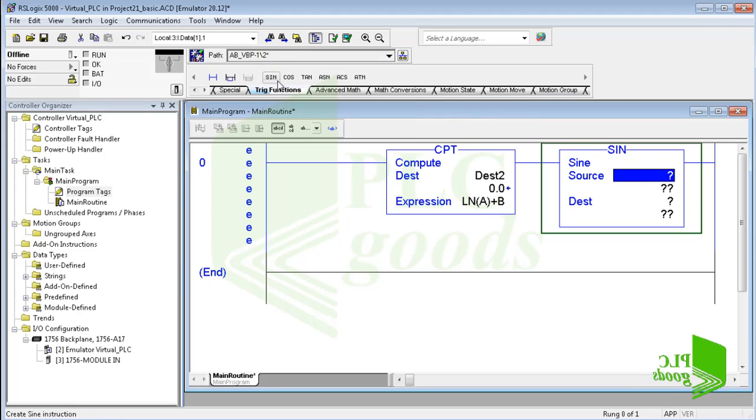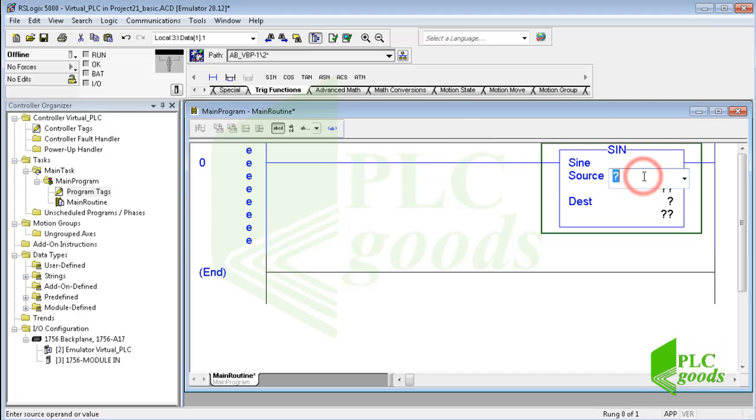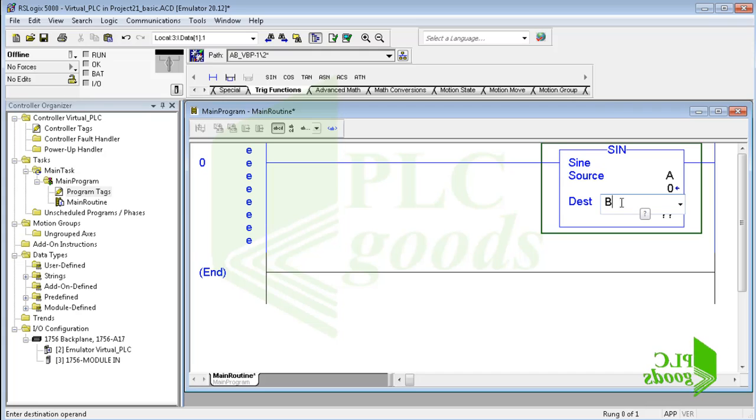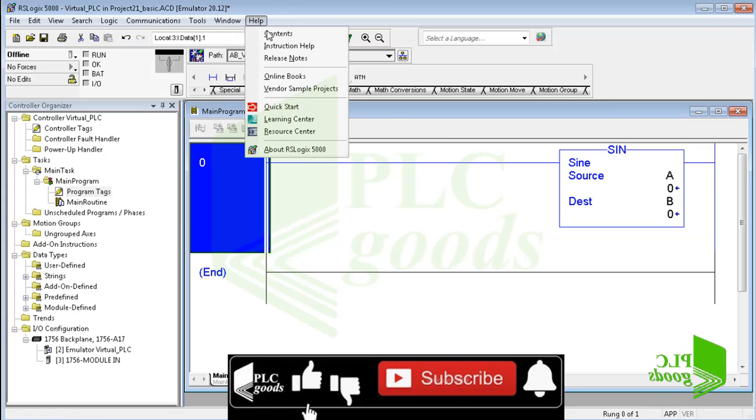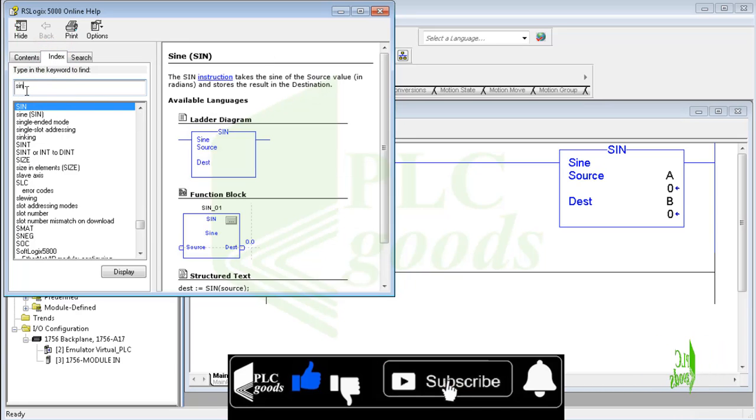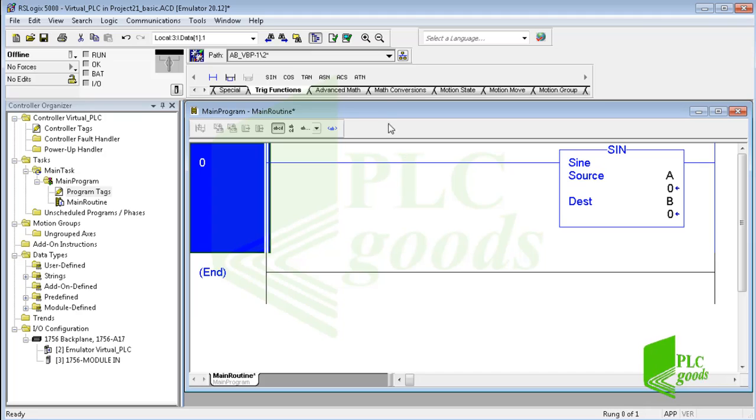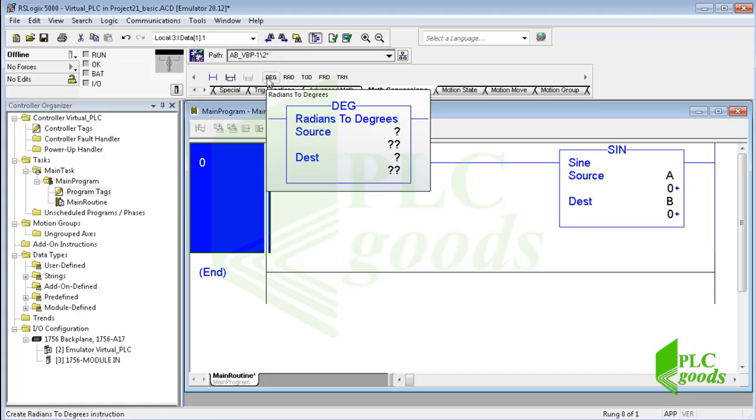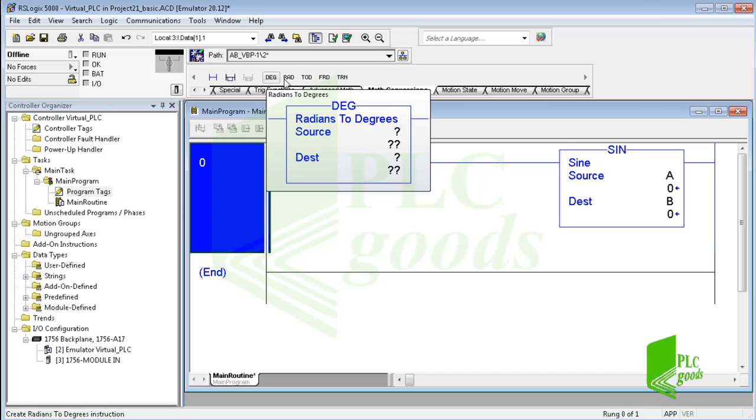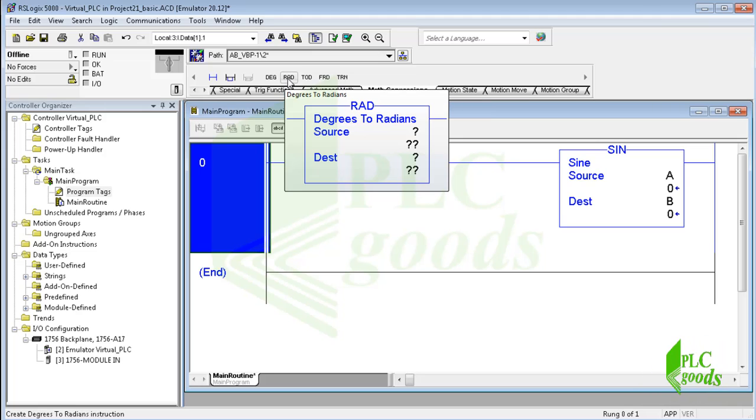Let me insert a sine instruction. Suppose we need to calculate the sine of 30 degrees and store its value on the B tag. Note that trigonometric functions like the inserted sine instruction work based on radian, so I need to convert 30 degrees to its equivalent radian. Let's look at math conversion instructions. The DEG instruction converts the source value in radians to degrees and stores the result in the destination address. The RAD instruction works inversely. It converts the source value in degrees to radians.